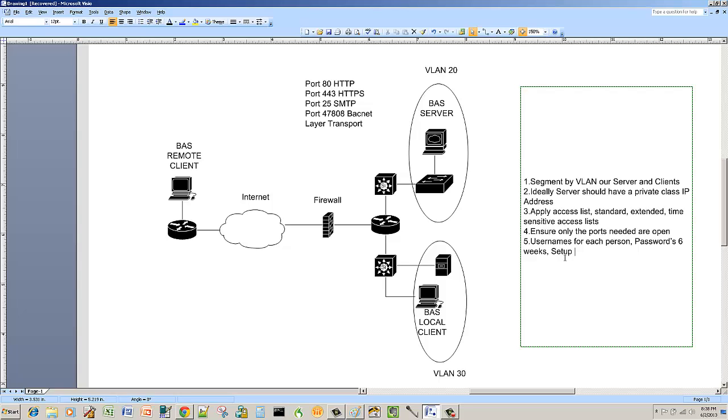Alright, and finally, set up access. Don't make everyone the administrator. That way they can go and delete audit logs and all sorts of stuff. Set things up in such a way that each person has the appropriate access to the right systems. Some people may not need access to Building 4 or Elementary School A, so don't give it to them. Don't allow them to have access to that automation engine or to that server.